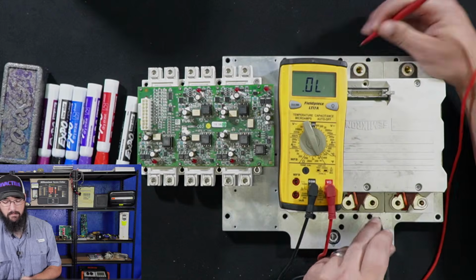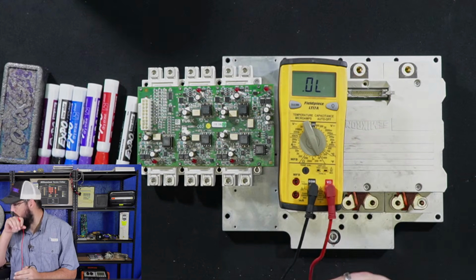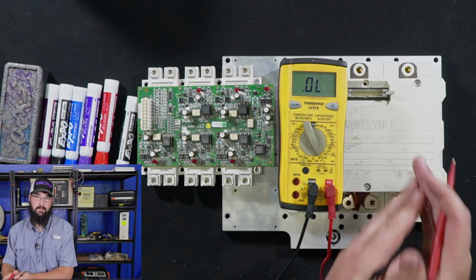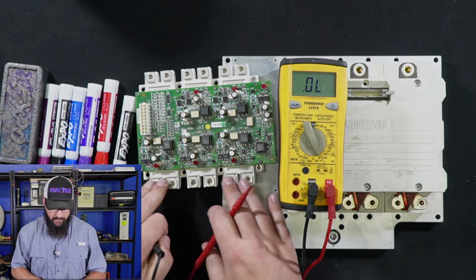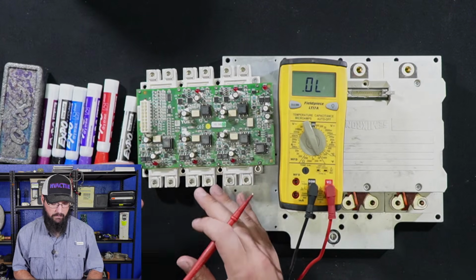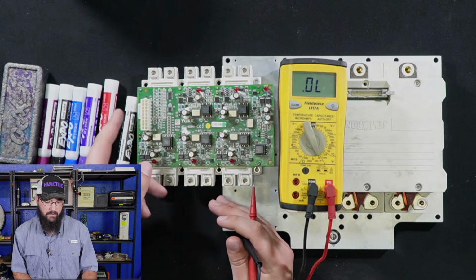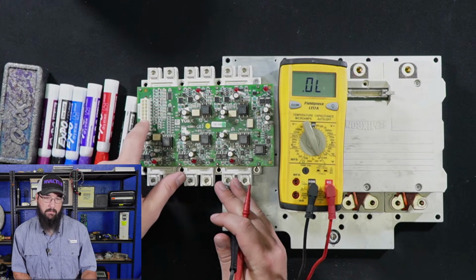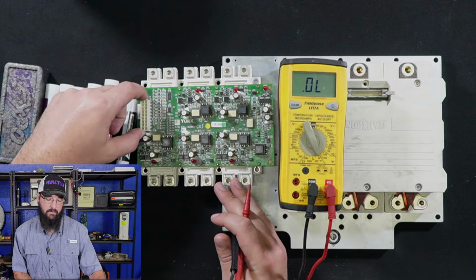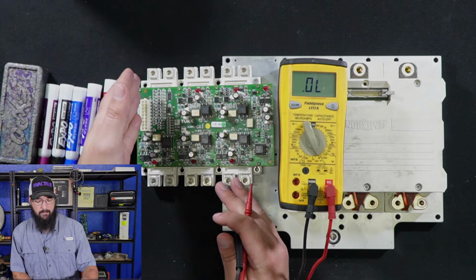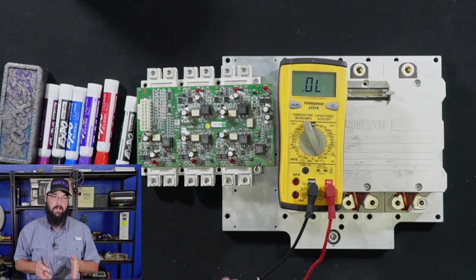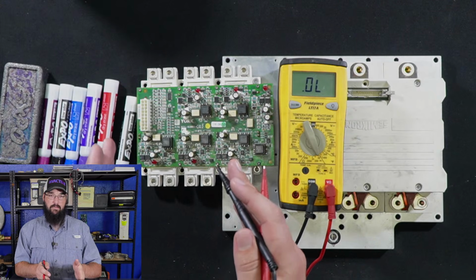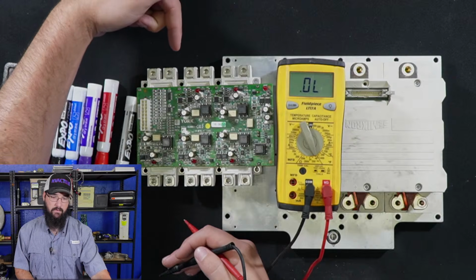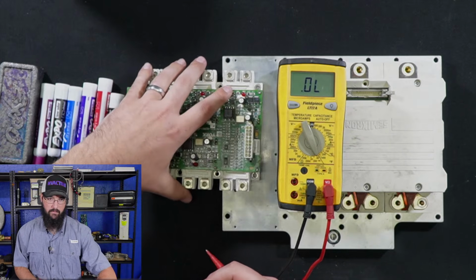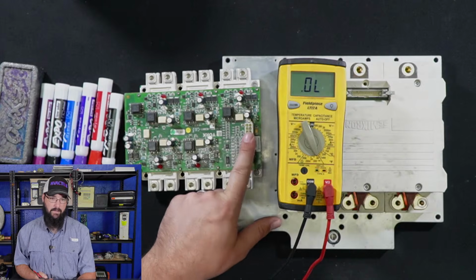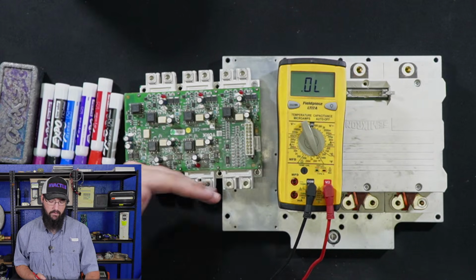And OL. Excellent. So these two measured relatively identically. Cool. Now, this is my input side, this is my output side of this module. The way that I always track with these is my 16-pin bus or Molex plug always goes on the, from this angle, technically I'm looking from the back of the drive forward. Technically, we would be servicing it from this way. So if I was sitting in front of the panel, this would be on my right-hand side, and with this on the right-hand side, I know that this is my output.